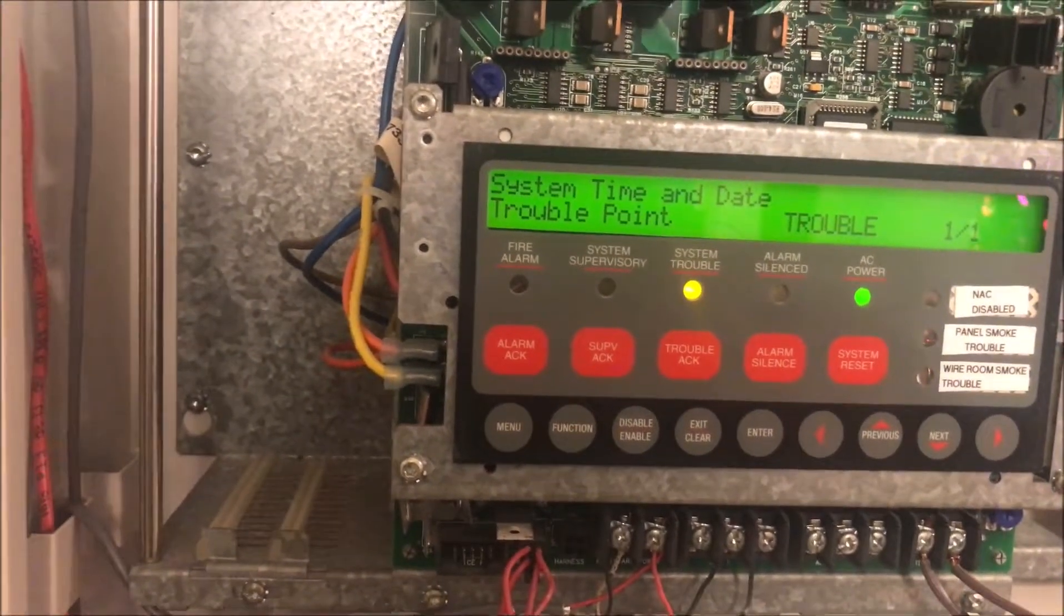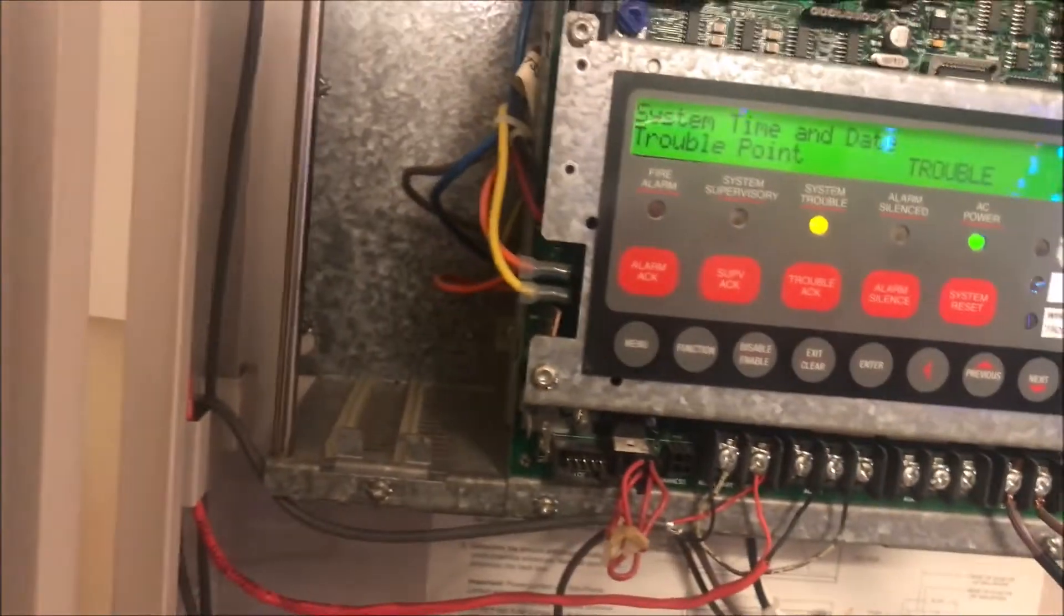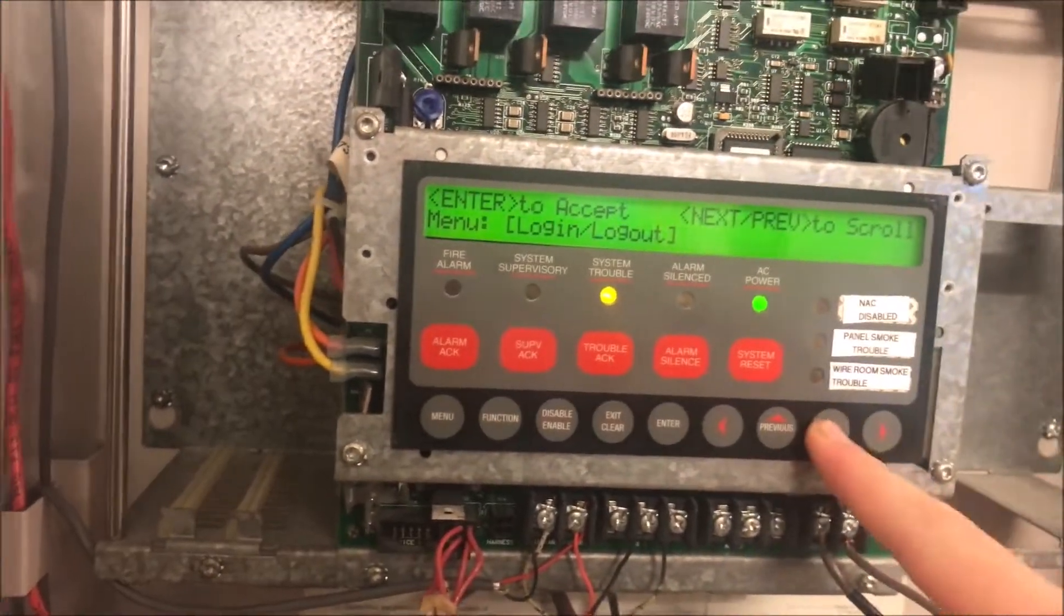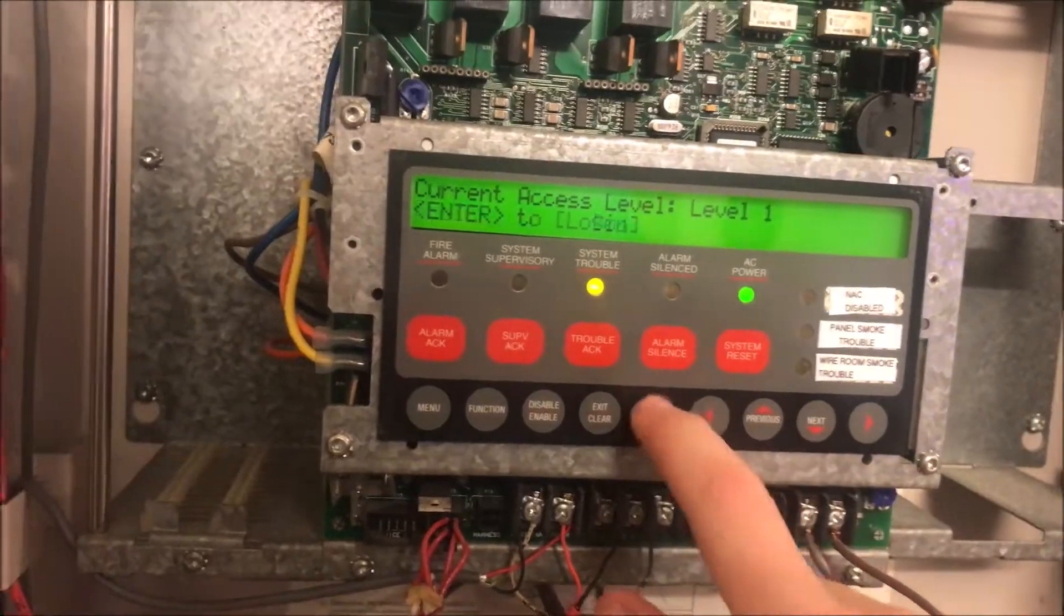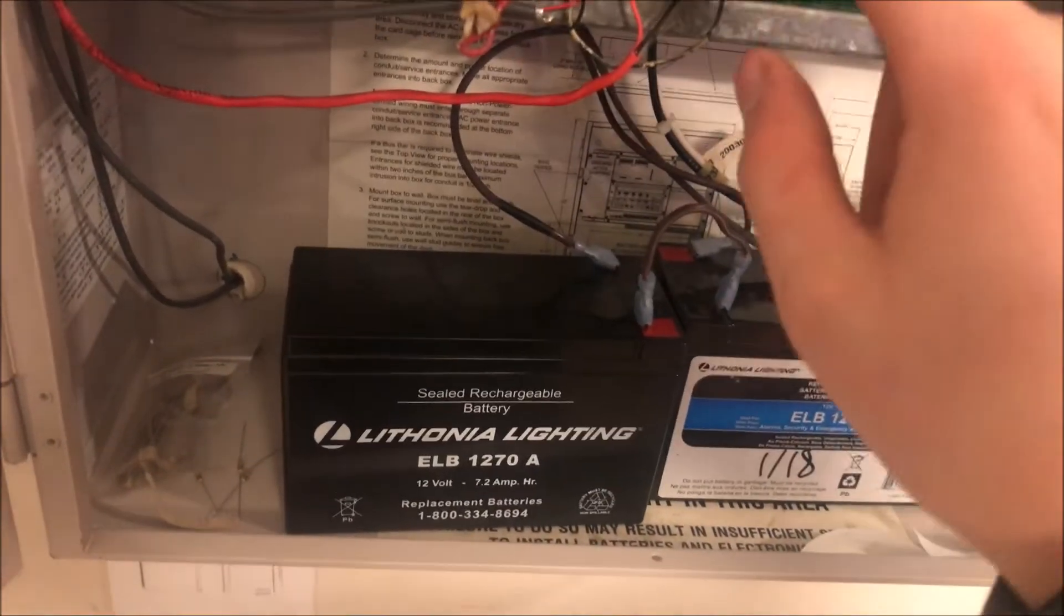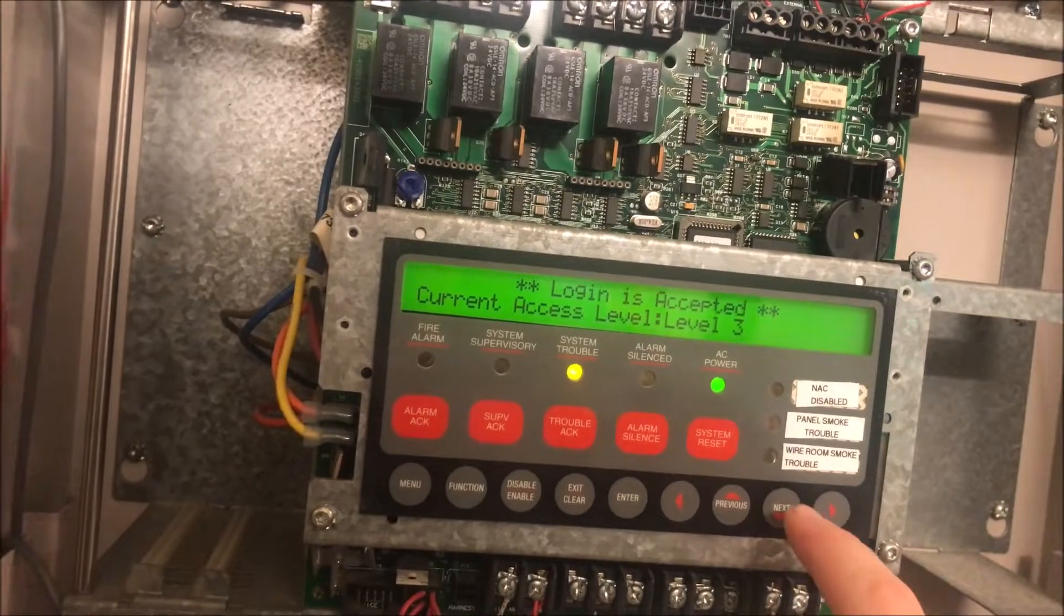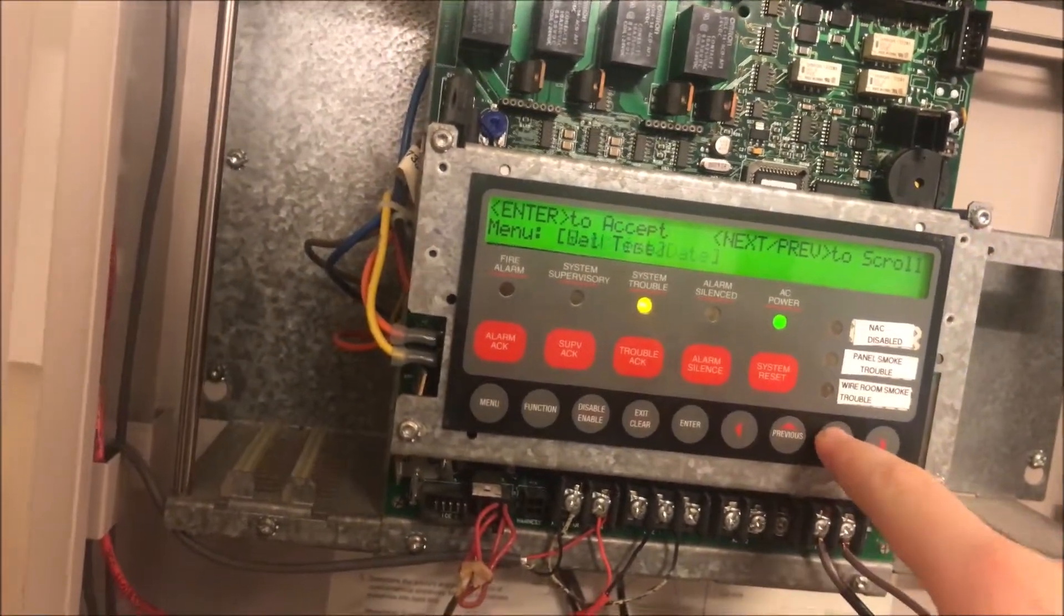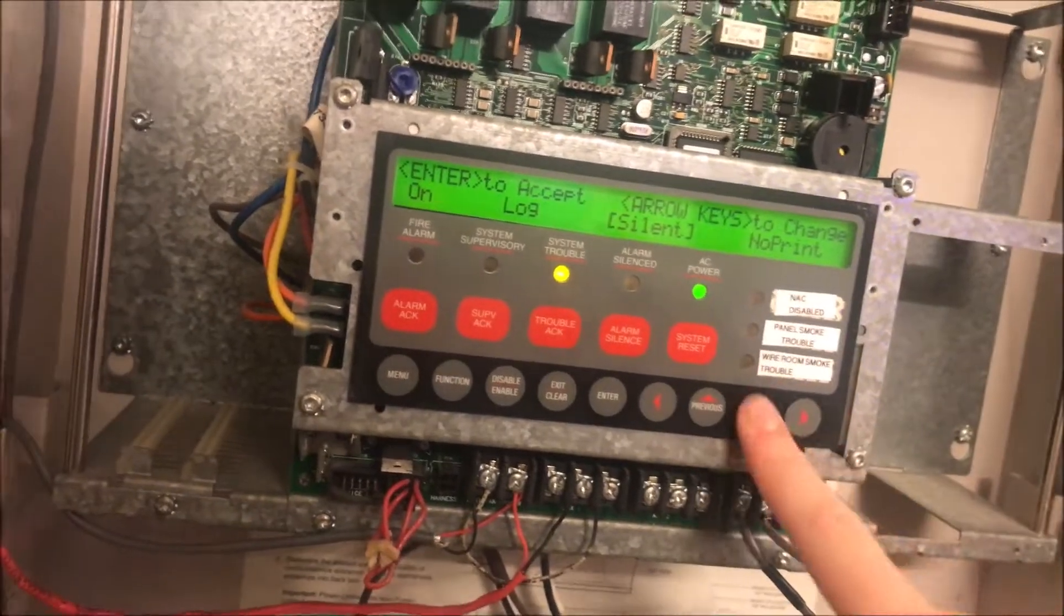So that was setting up a new IDnet point on a Simplex 4010 fire alarm control panel. What we are going to do real quick is we are going to walk test it just to make sure it works. We'll log into our level three and we will put the panel in walk test with signal.